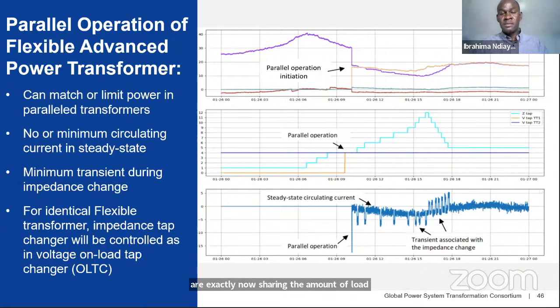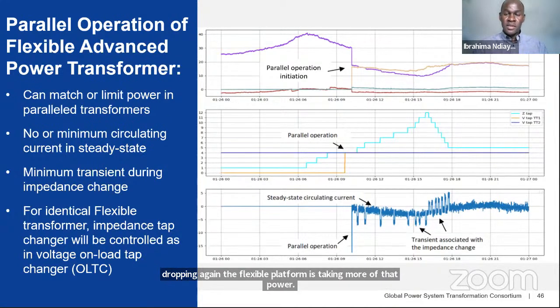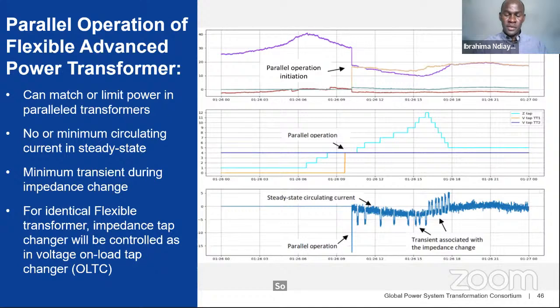And obviously, when you increase the impedance value at the flexible transformer, that transformer is taking less power, which is the purple curve, compared to the other transformer, which doesn't have the capability to change its impedance. And then rightfully so, when we reach the maximum impedance and start dropping again, the flexible transformer is taking more of that power.